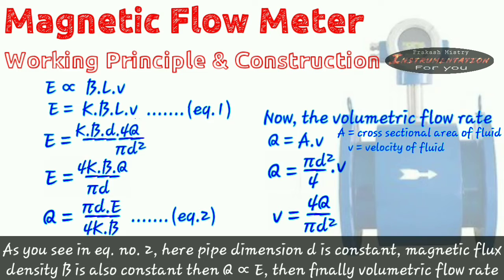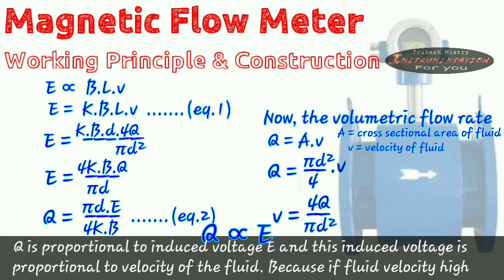Then as you see in equation number 2, here pipe dimension D is constant. Magnetic flux density B is also constant. Then Q is proportional to E. That means now finally volumetric flow rate Q is proportional to induced voltage E.